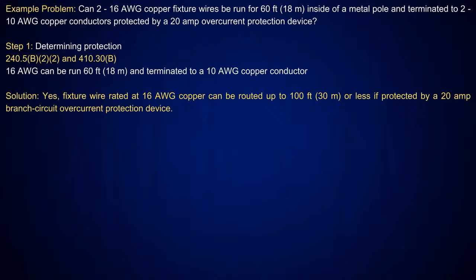Mm-hmm. Well, and see, here's a good one. What if I'm inside a pole? Okay. I've got two number 16 copper fixture wires that run 60 foot inside the metal pole and terminated to two number 10 copper conductors protected by a 20 amp overcurrent device. Can I do that? Well, yes, you can do that, because if you go look at 240.5B22 and also tie that in with 410.30B, they're going to tell you those number 16s can be run that 60 foot and terminated to a number 10 conductor.